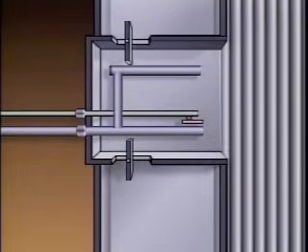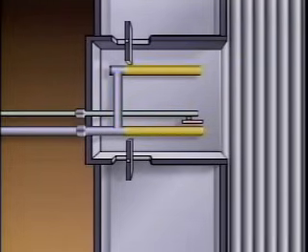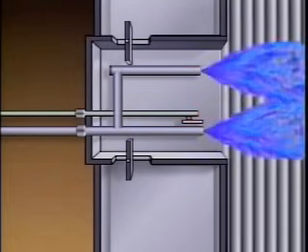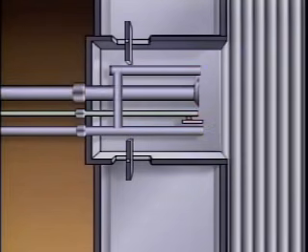In a typical natural gas burner, the gas is fed under pressure from the gas supply to a burner manifold. From the manifold, the gas flows into pipes called gas spuds. Holes in the ends of the spuds direct the gas into the boiler furnace. Some boilers have burners that can be used with more than one type of fuel — for instance, this burner has both gas spuds and an oil nozzle.